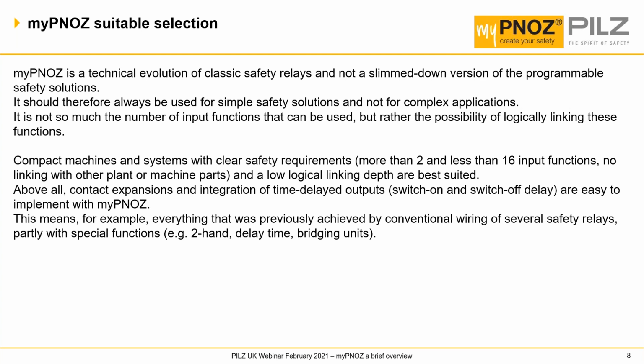For instance, 2 to 16 inputs, simple logic functions, no linking with other parts of plant or mechanical parts, machine parts. Above all, contact expansions and integration of time-delayed outputs, switch on and switch off delay, are easy to implement with the myPNOZ. This means, for example, everything that was previously achieved by the conventional wiring of several safety relays, partly with special functions, for example, two-handed control, delay times and bridging of one or more units, is suited to this system.